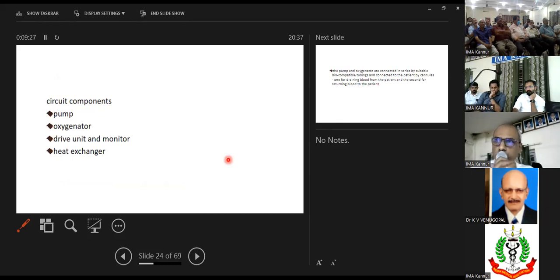The pumps which we use for extracorporeal life support are, now when you think about fluid pumps, you have basically two types. One is what we use in the heart-lung machine, which is a roller pump. There, a set of rollers actually squeezes the tube in one direction so that the fluid keeps flowing in that direction only. That is something which is useful for short runs, but not for prolonged usage for many days or weeks. And in ECMO, what we use is a centrifugal pump where there is no actual physical squeezing of the blood.